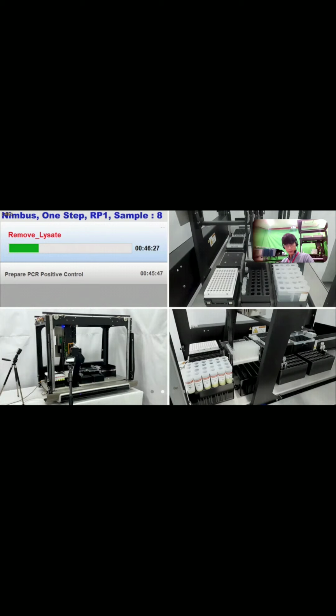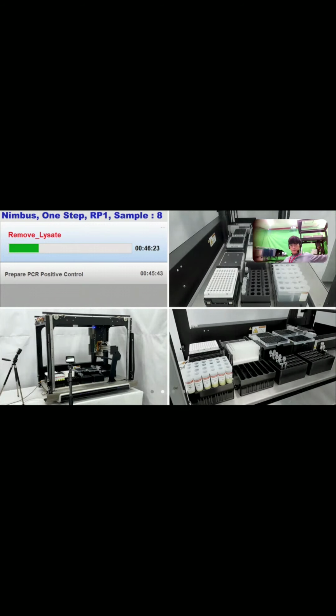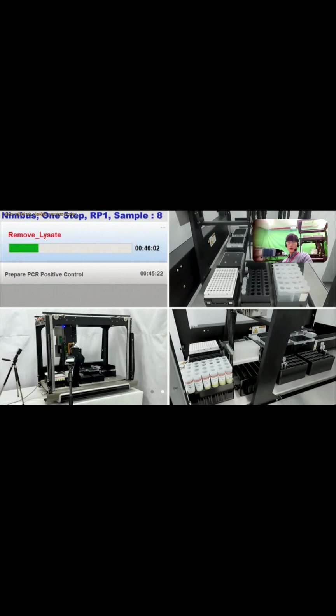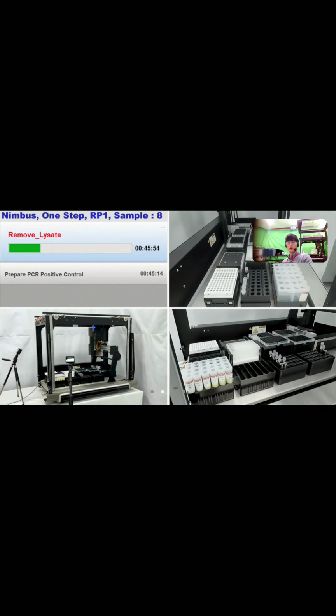We need to prepare this step. We need to stop it. The timing is in this video. I have 8 samples. So when the tip is aspirated, the very last sample, when the tip is reaching, which aspirates the last sample and is ejected, at this moment you just select the pause button in the method software.